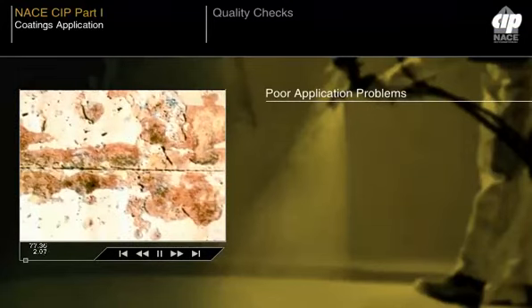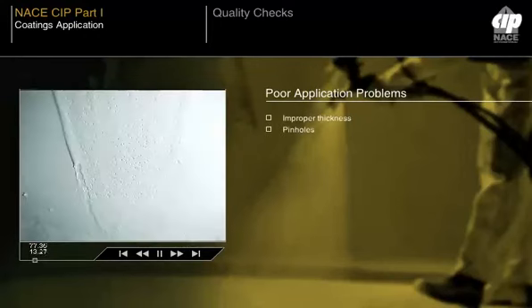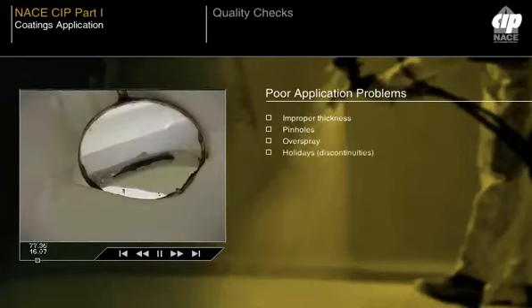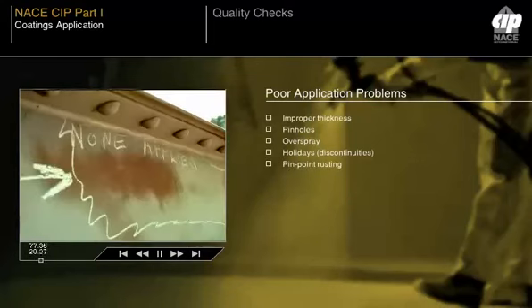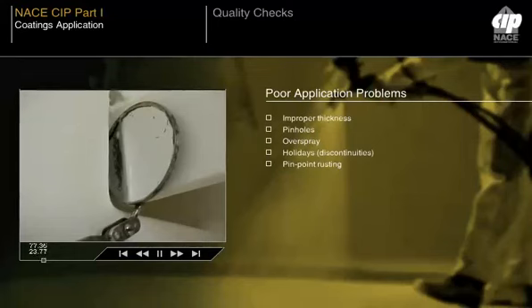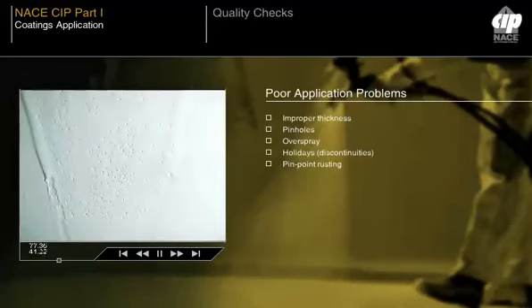Poor coating application is a major factor which causes failure. Typical problems resulting from faulty application techniques might include improper thickness, pinholes, overspray, holidays, discontinuities, pinpoint rusting. Almost all application-related failures are due to poor workmanship, though this may sound like harsh judgment. Poor workmanship refers to such practical issues as holding the spray gun too close or too far away from the surface, or at a significant angle to the surface being coated. These matters are largely a question of training or the lack of it, leading to a simple lack of understanding of what causes paint application problems.